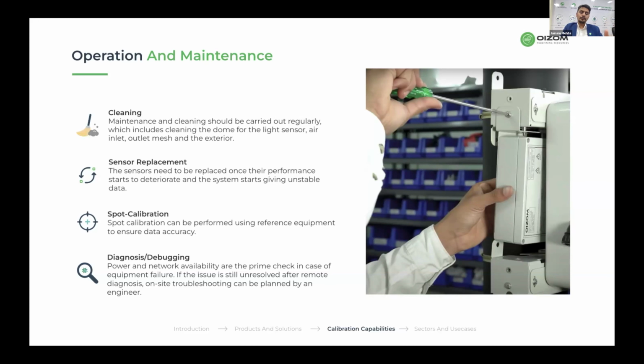Similarly, spot calibration can be done. There are two options: you can calibrate the system using gas cylinders, as we spoke about, zero and span gas calibration. Or for spot calibration, you can install a station next to a reference analyzer and correlate the data to update the necessary compensation correction algorithms. Or you could get a freshly calibrated Oizom unit, deploy it next to the existing station - one acts as master, the other as slave - and apply the necessary compensation correction algorithms there as well.